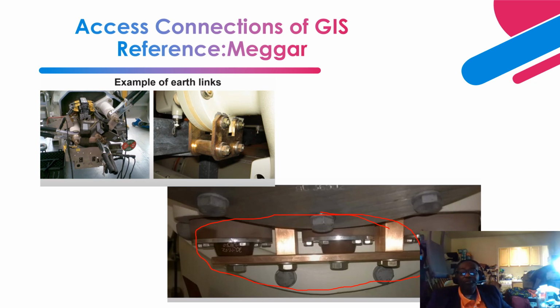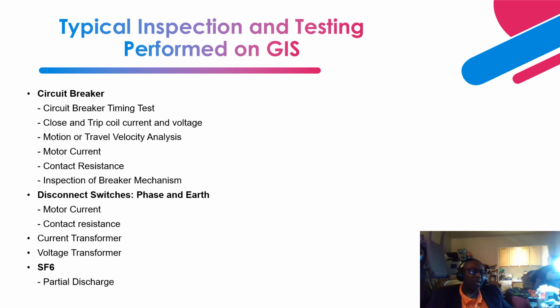Now let's take a look at the typical inspection and testing performed on the GIS. This usually comes into play after, let's say, 10 to 12 years of the GIS being in operation. For the circuit breaker, you perform the circuit breaker timing test. Then you also perform the close and trip coil current and voltage test.